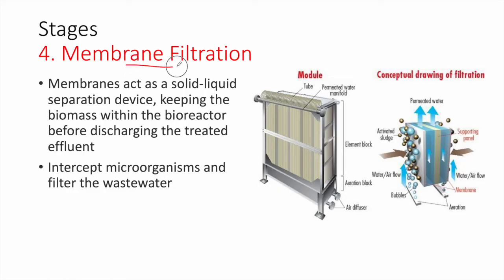Next, we have the membrane filtration. If we are using modules, a module is submerged into the wastewater with air diffusion. The membrane filtration requires aerobic conditions. Water enters through these membranes and we get clean water — what we call permeate — along with the formation of activated sludge. This happens in aerobic conditions through aeration, which has two objectives: to create aerobic conditions and to clean the MBR sheets. The membranes act as a solid-liquid separation device, keeping the biomass within the bioreactor before discharging the treated effluent.